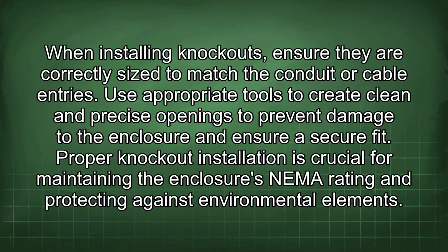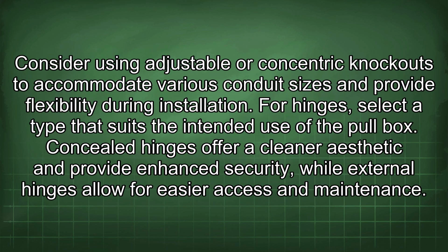When installing knockouts, ensure they are correctly sized to match the conduit or cable entries. Use appropriate tools to create clean and precise openings to prevent damage to the enclosure and ensure a secure fit. Proper knockout installation is crucial for maintaining the enclosure's NEMA rating and protecting against environmental elements. Consider using adjustable or concentric knockouts to accommodate various conduit sizes and provide flexibility during installation.